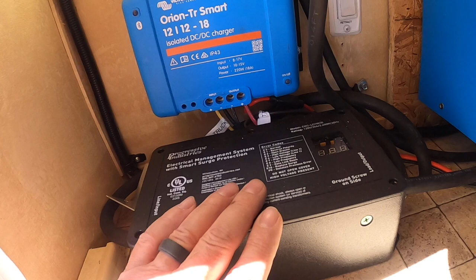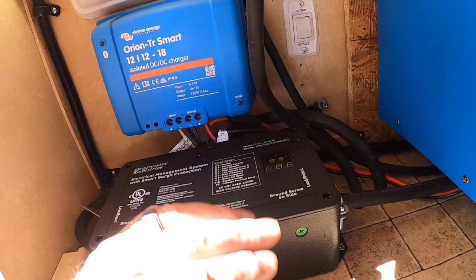All of my shore power comes all the way from the back corner, the driver's side back corner of the RV, into my Progressive Industries Electrical Management System, or EMS for short - no pun intended. This monitors frequency, both low and high, as well as low and high voltage, and any miswiring like neutral and line reversed, say if you're plugging into somebody's garage that's wired wrong, giving me codes for any issue. Within milliseconds, if it detects a problem, the relay drops out and disconnects all power from the RV before it can fry your electronics, like your refrigerator, stereo, or TV.